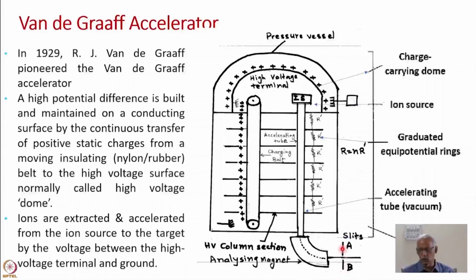Here you can see there are two slits. The opening is only 1 or 2 millimeter, and through it the particles with the exact energy will go. If the energy changes because of a change in the voltage, the particle will fall either on A or B, depending upon whether the energy has increased or decreased. If it is falling on A, that means the energy is low. If it is falling on B, that means the energy has increased. Energy is directly proportional to the voltage. That means there is a variation and that has to be corrected.